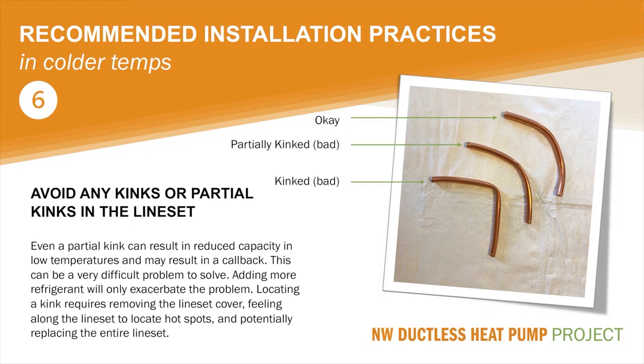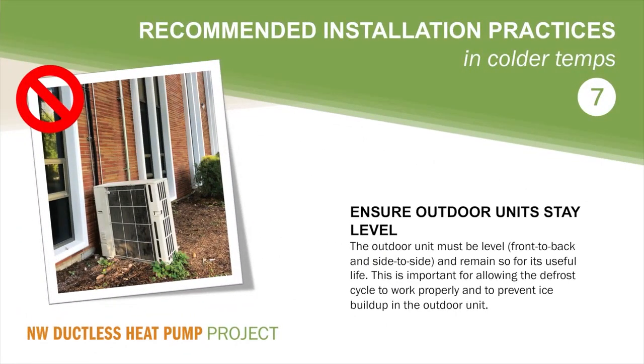Locating a partial kink requires removing the line set covers and feeling along the line set. When you feel a hot spot, this is the location of a partial kink. Typically, the solution is to replace the entire line set. Our next recommended installation practice involves ensuring the outdoor unit stays level.